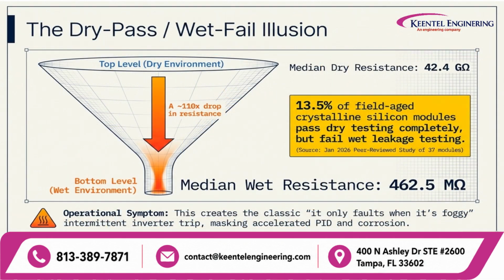Dielectric integrity in solar arrays suffers from a dangerous dry environment illusion. Field data reveals that 13.5% of field-aged crystalline modules completely pass standard dry insulation resistance testing, yet immediately fail under wet conditions. As shown here, median resistance drops by approximately 110 times, plunging from over 42 gigaohms down to 462 megaohms when exposed to moisture. In operations, this manifests as unexplained early morning ground faults during humid or foggy conditions, accelerating PID and conductor corrosion long before a total fault registers.